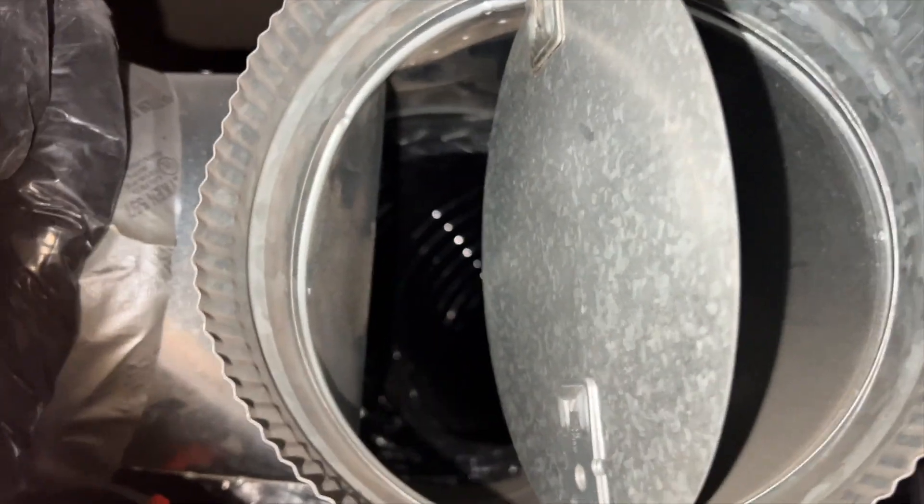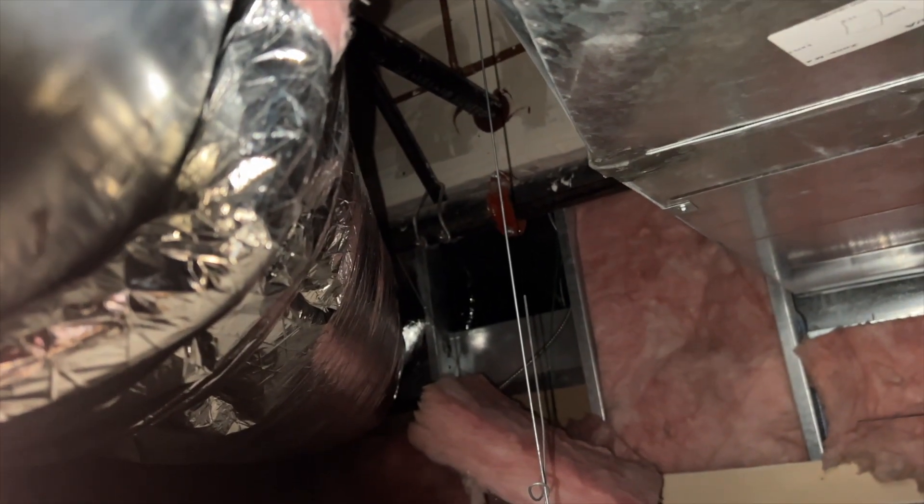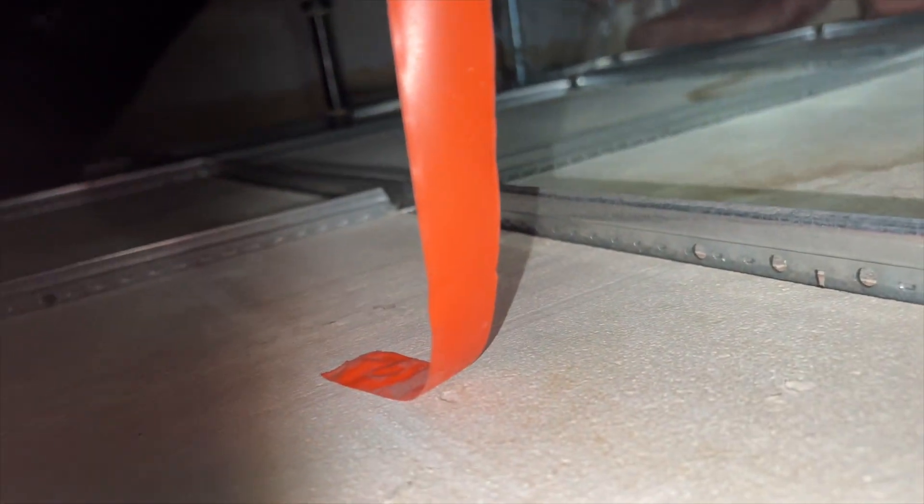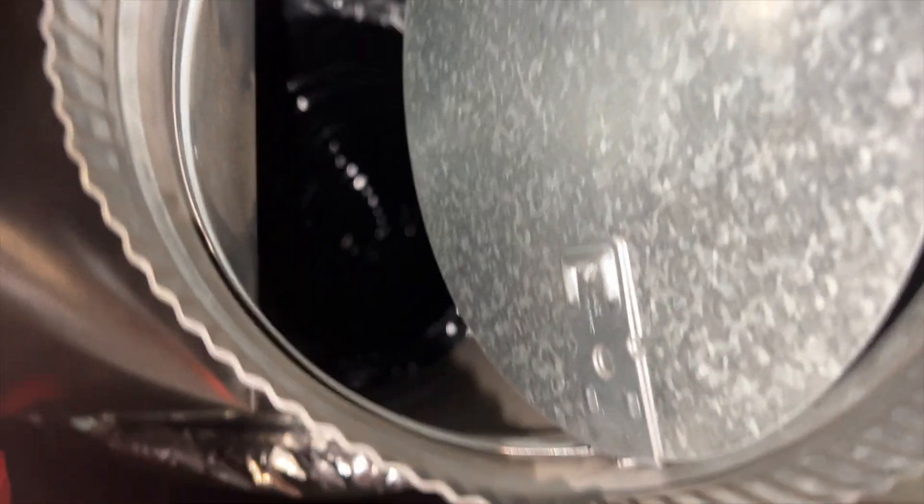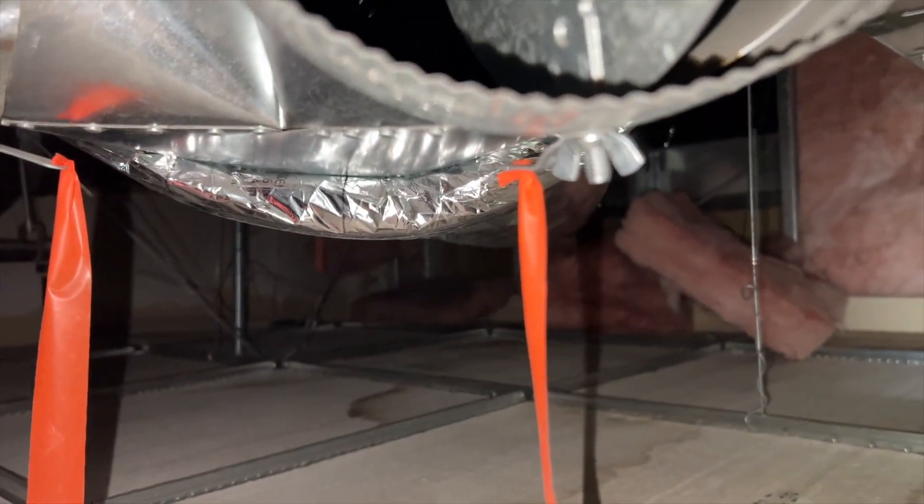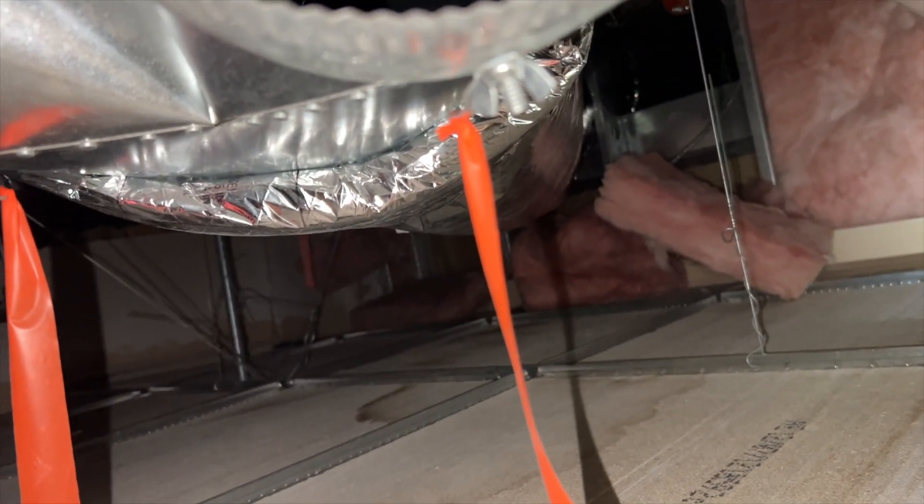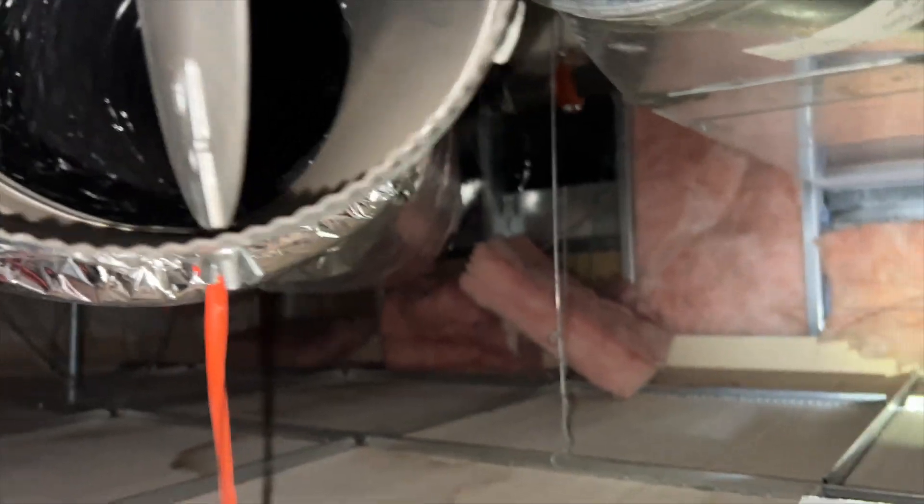This is completely off. I am actually getting a little bit of cold air coming out here but it's very faint, so it looks like it runs back over there somewhere. There's another suite on the other side of there, so we're gonna have to get in there. I'm getting a little bit of airflow out of it but very very little, so I think the damper is not opening all the way. See it's cold, feels good here blowing in my face. We're gonna reattach this with some duct tape and then we'll go find the damper which is definitely going to be in that other suite.